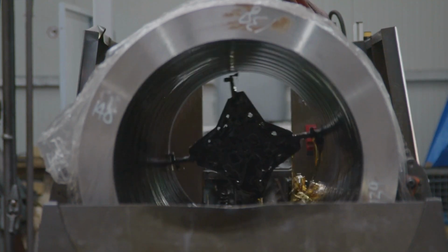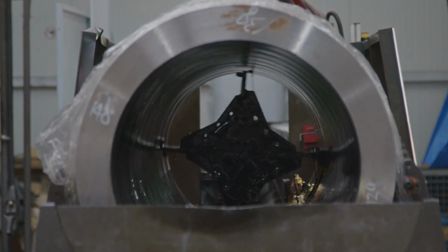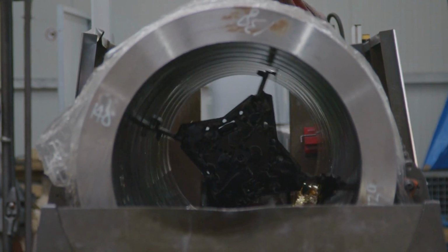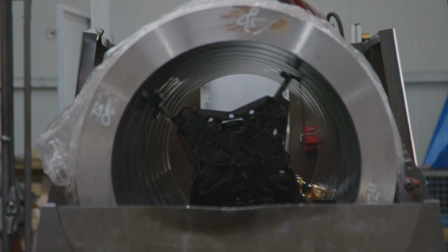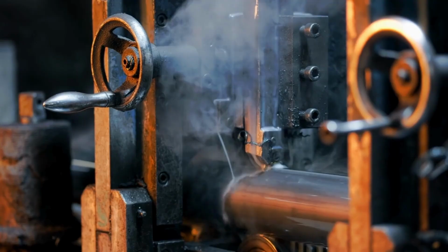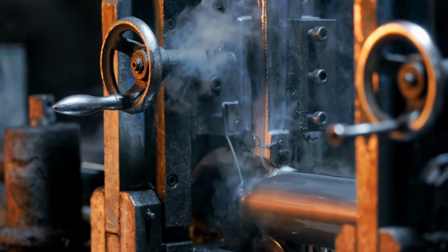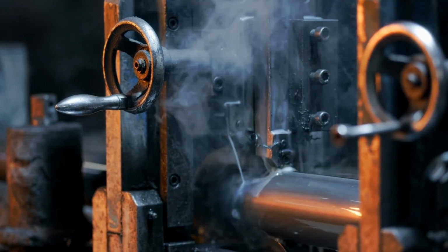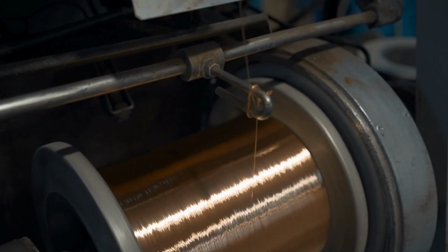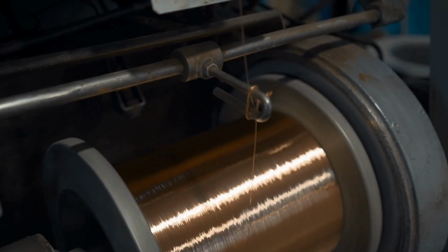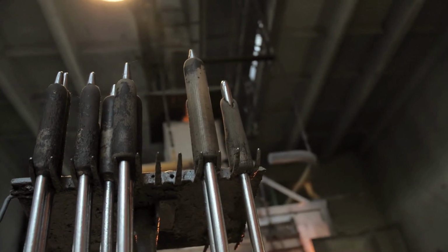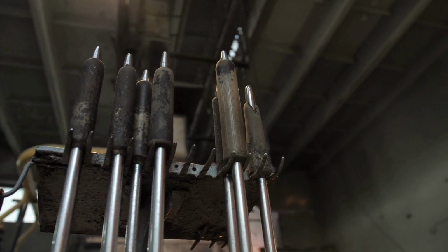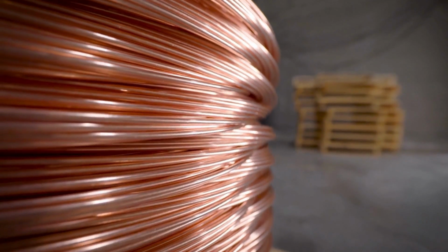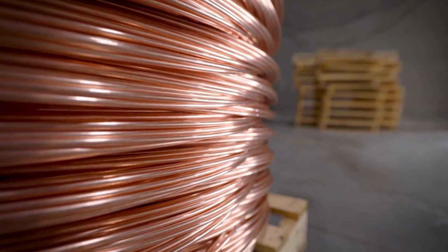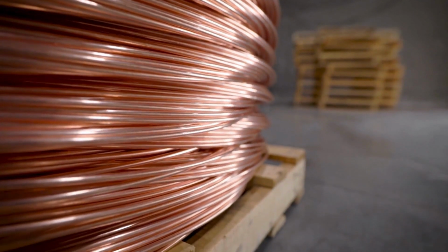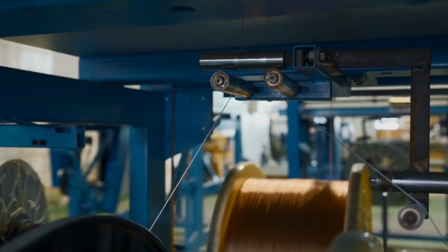The copper conductor is responsible for carrying electrical current from one point to another. Its properties directly determine how efficiently electricity flows, how much current the wire can safely carry without overheating, and how well the wire can tolerate bending, twisting, and vibration during installation and use. The insulation layer plays an equally critical role, even though it does not carry current itself. It electrically isolates the conductor, prevents short circuits, protects users from electric shock, and shields the copper from environmental factors such as moisture, heat, chemicals, and mechanical abrasion. In many applications, the insulation is the last line of defense between safe operation and catastrophic electrical failure.